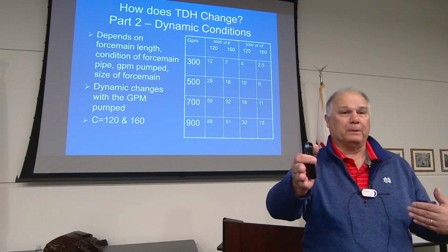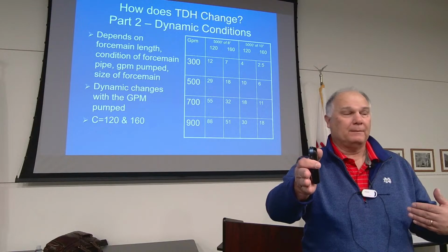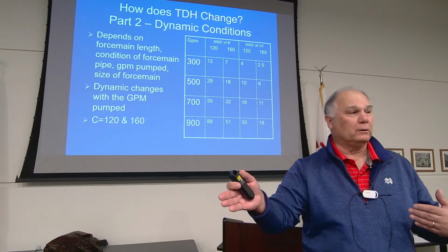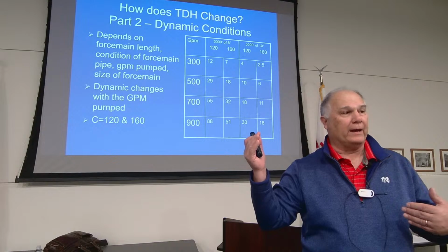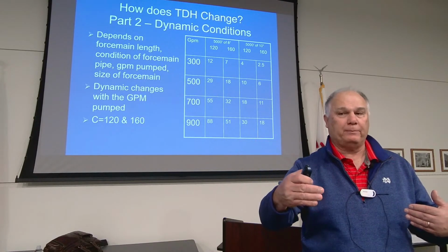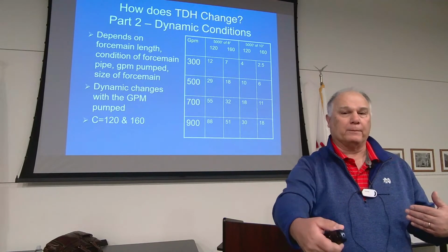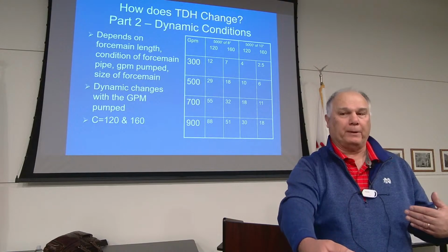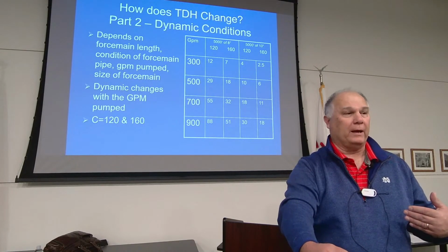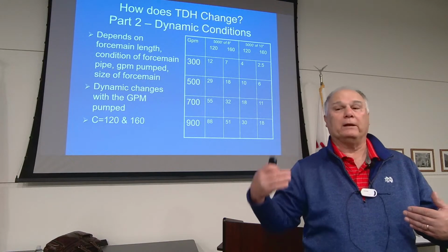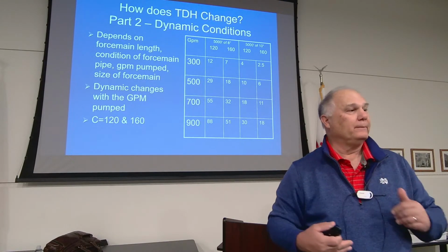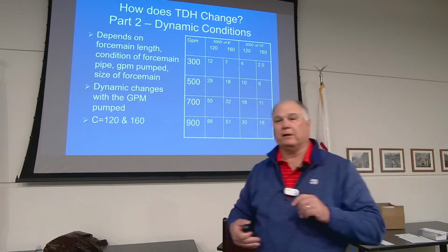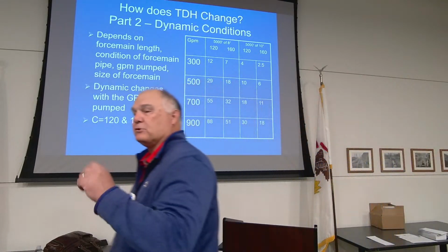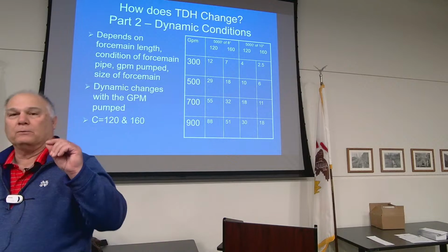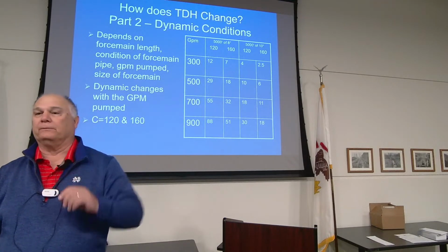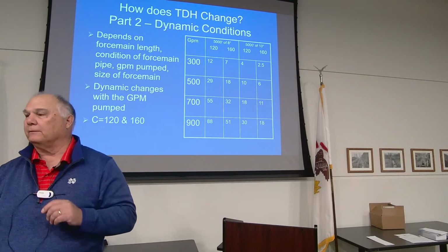Why are we going to exceed that pump station volume? Because our friction is lower because we have a higher C factor. A higher C factor means really slick pipe. A lower C factor, a lower number, means a really Barnacle Bill pipe. By doing that, we are going to exceed our station. So what's the first thing you guys do when you get a brand new station? You put it in service, and what does the engineer, what do the city guys, what does everybody do? I want to make sure that we didn't screw up.